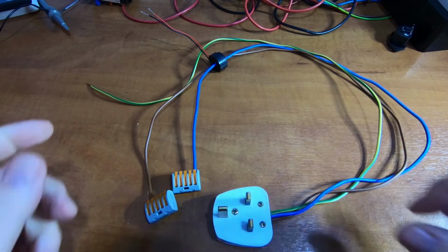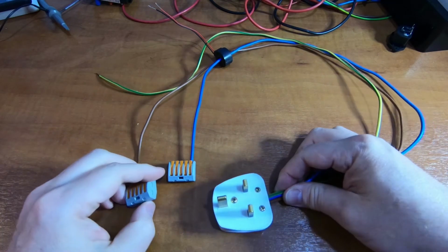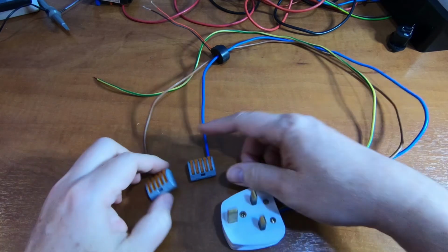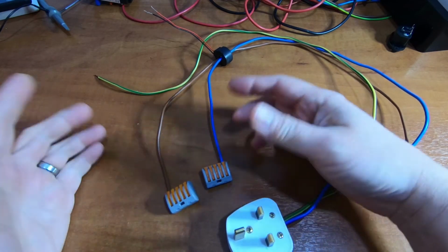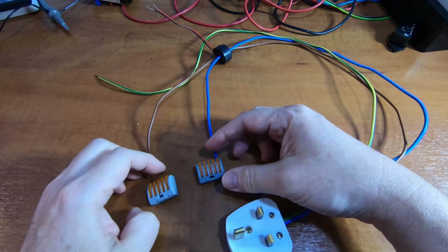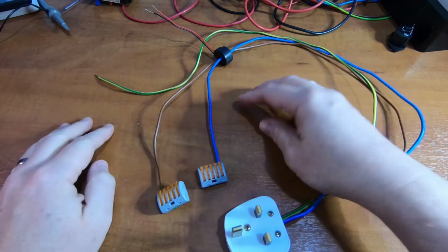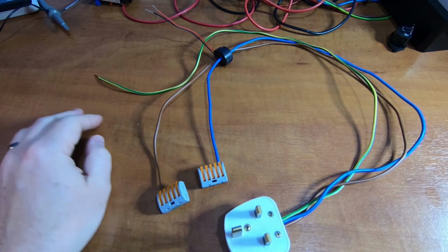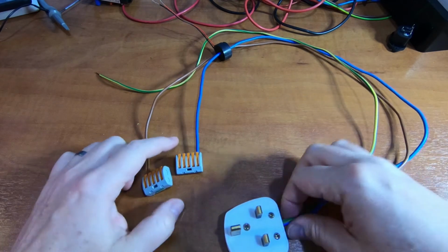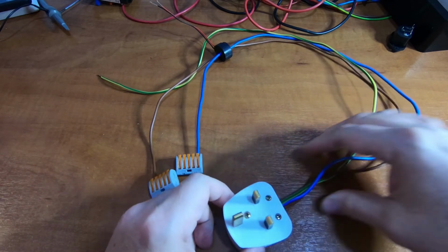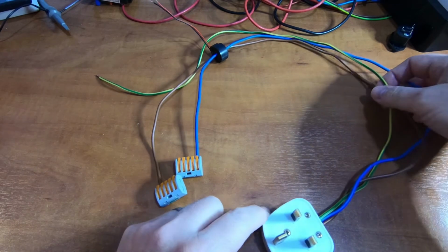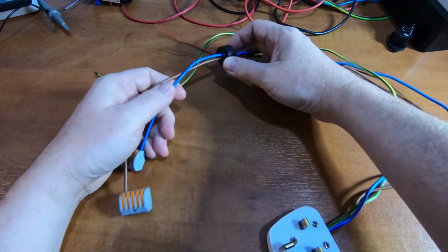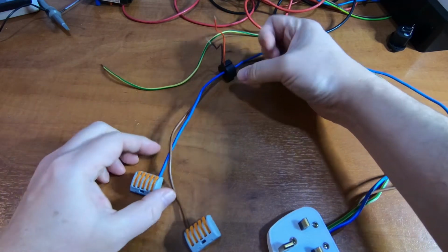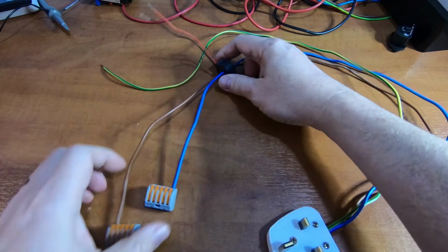So what I have here is a test cable I've made up, and this is going to allow me to generate an example of earth leakage. The way I'm going to do that - this is going into the mains socket. We've got live, neutral, and earth. We don't actually need the neutral for this test.